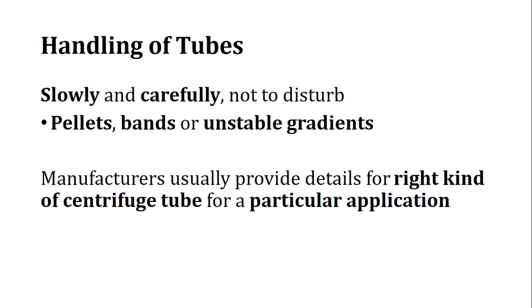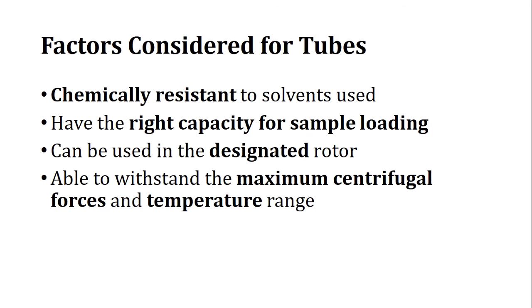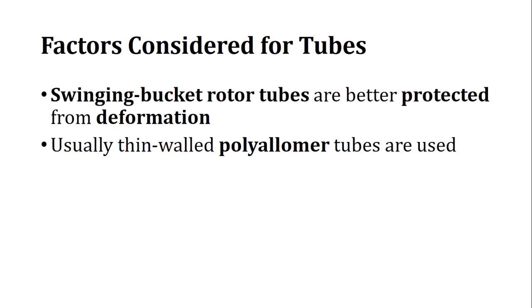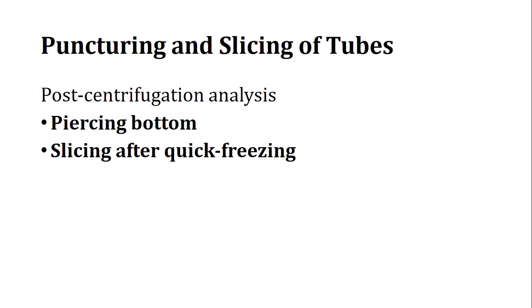Manufacturers usually provide details for the right kind of centrifuge tube for a particular application and those instructions should be followed. Key factors for tube selection include: chemical resistance to solvents used, right capacity for sample loading, compatibility with designated rotors, and ability to withstand the maximum centrifugal force and temperature ranges. Thick-walled tubes in a fixed angle rotor at high RCF can collapse. Swinging bucket rotor tubes are better protected from deformation; thin-walled polyallomer tubes are typically used for swinging bucket rotors.